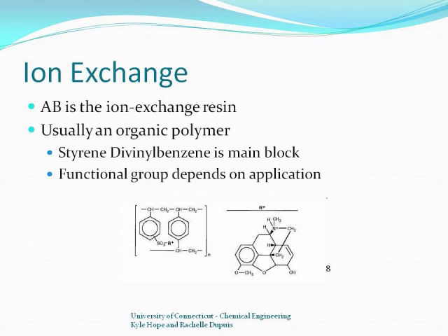An ion exchange resin is normally an organic copolymer known as styrene divinyl benzene. The image on the left is the repeating block of the polymer, and it has been sulfonated to provide a functional group, a common practice in industry. The functional group is what we're interested in, and for different applications, different functional groups are used.